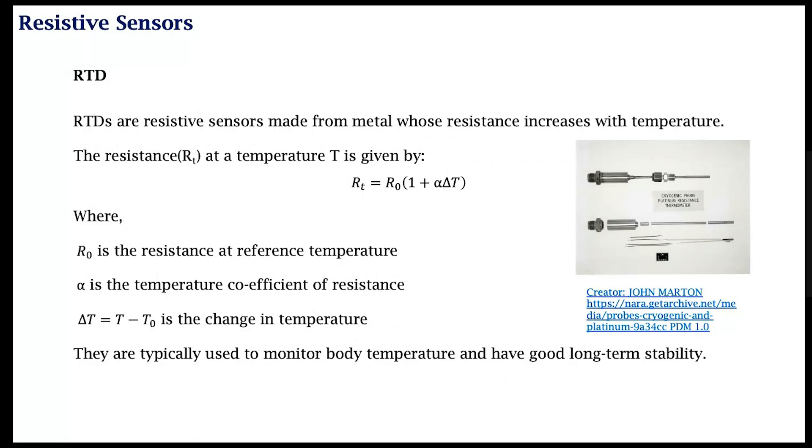Another device is the RTD. These are resistive sensors that are usually made of metal whose resistance relatively linearly changes with change or increase in temperature. So this is relatively linear. In this case, the measured temperature is Rt and the reference temperature is some R0, and there is a temperature coefficient α and a delta T, which is T minus T0.